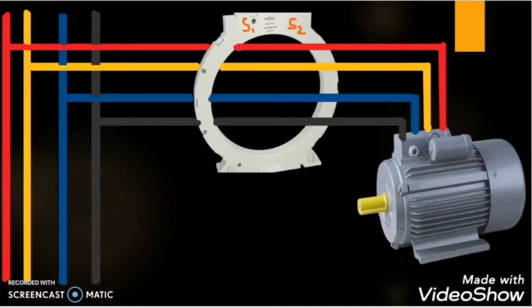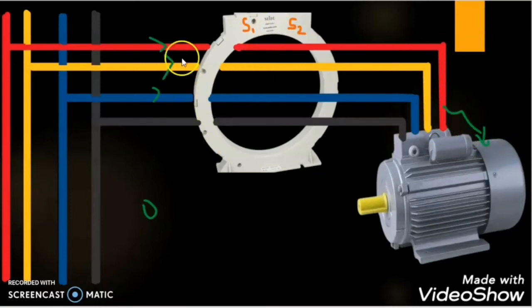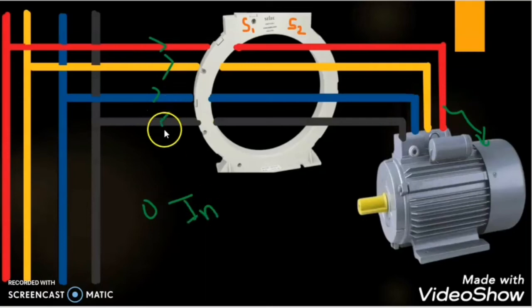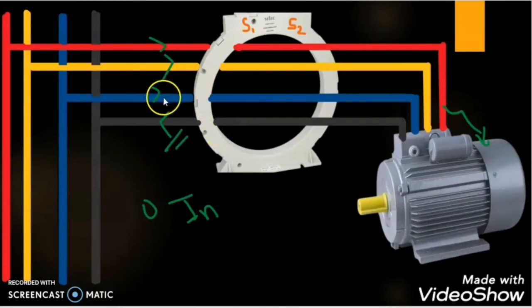The concept explained through the single phase system is the same for the three phase system. If the current IR plus IY plus IB is 0, the CBCT will not activate itself. But whenever there is an earth leakage fault in any phase, the resultant current between IR, IY, and IB will be some current, which we call neutral current. When the CBCT finds this current, it gives a signal to the relay and the relay operates accordingly. Now let us understand how to do the electrical wiring for ELR and CBCT in order to protect any load from earth fault current.